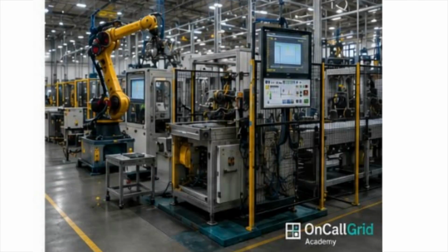Here's the thing, every plant, warehouse, and production line needs to run reliably, safely, and efficiently. That used to mean rooms full of hardwired relays. If you needed to change how something worked, you were rewiring panels by hand. PLCs, Programmable Logic Controllers, replaced all that. Same job, but now it's software instead of a wall of relays. Way easier to modify, troubleshoot, and expand. You'll find these things everywhere: conveyors, packaging lines, warehousing, manufacturing. If it moves, sorts, fills, or seals, there's probably a PLC behind it.